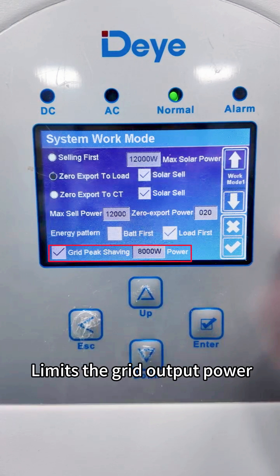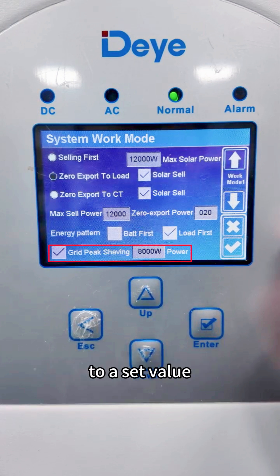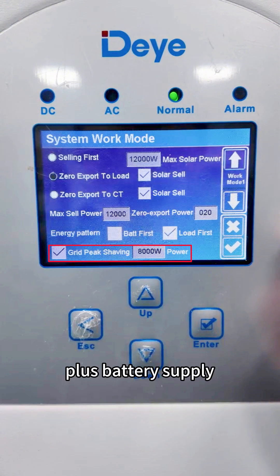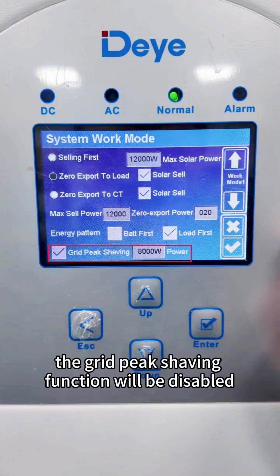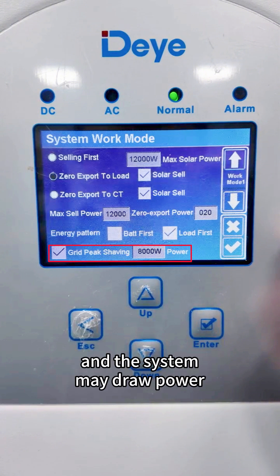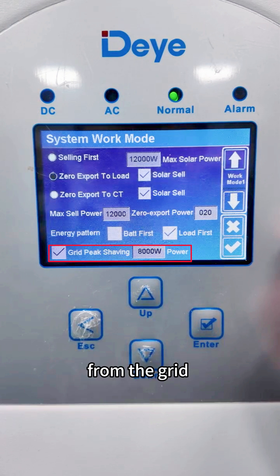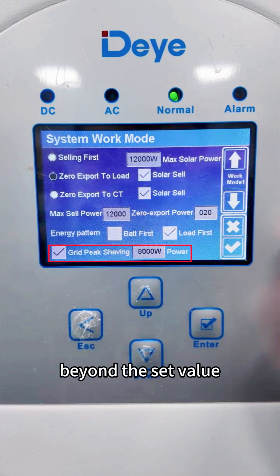Grid peak shaving limits the grid output power to a set value. If PV generation plus battery supply is insufficient to support the loads, the grid peak shaving function will be disabled, and the system may draw power from the grid beyond the set value.